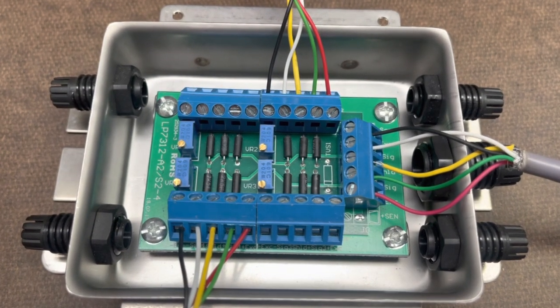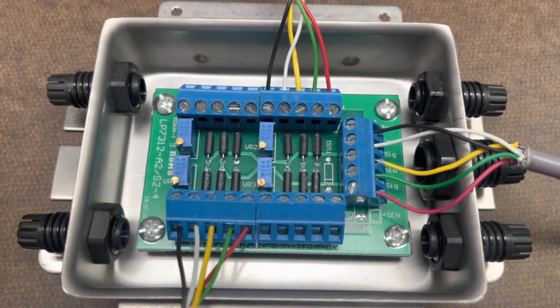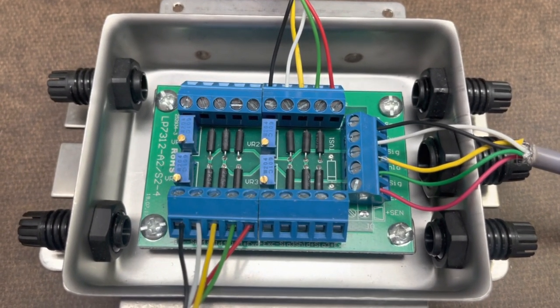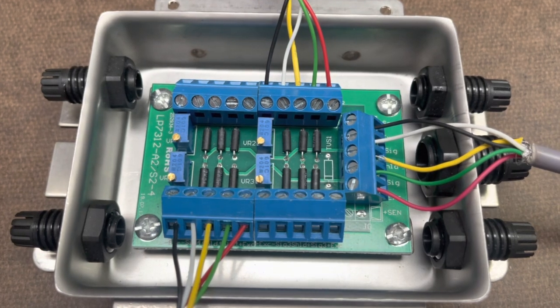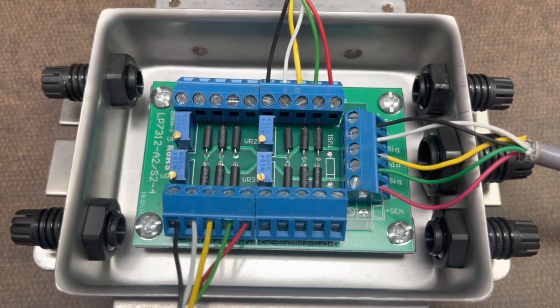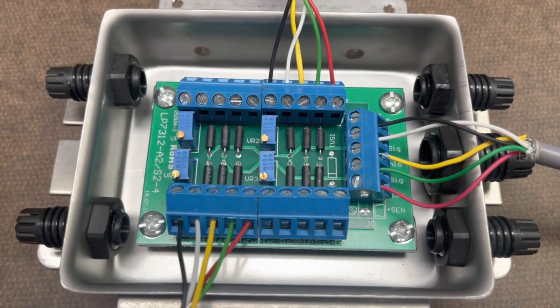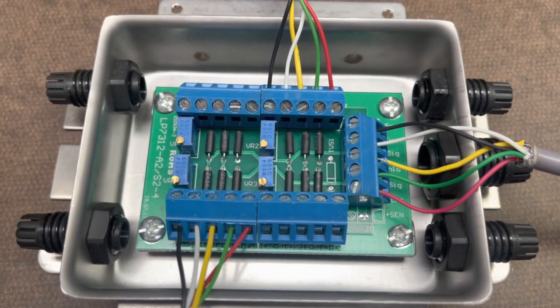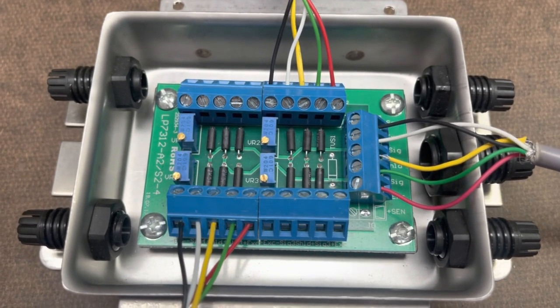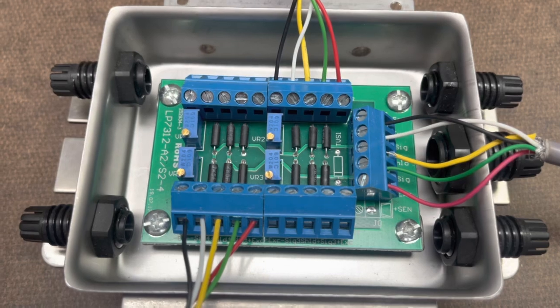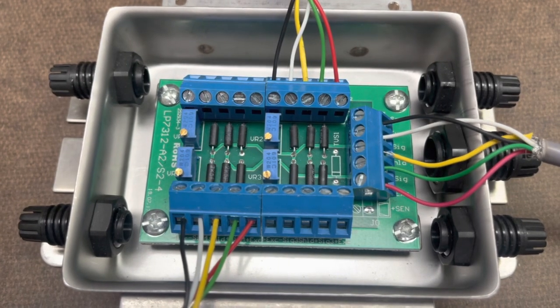If you've installed a load cell the incorrect way, or maybe the factory installed it incorrectly, and you're not getting any readings, this is how you could switch your signal wire.